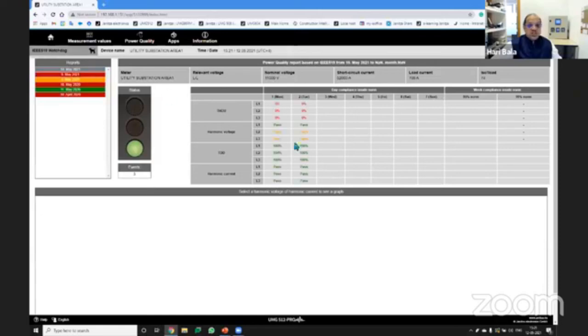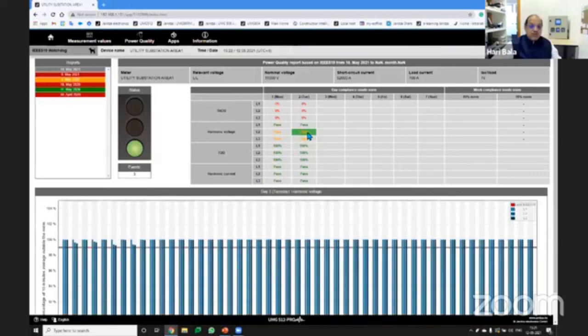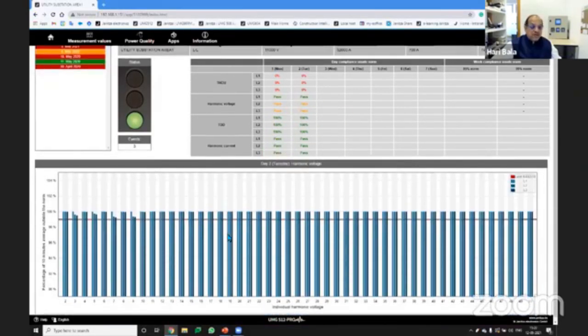For this, I have it installed for 2 days. Since I'm using a single phase supply, it can be wrong, but the essence of what I wanted to show you here is THDU, harmonic voltage, TDD, and harmonic current. If I want to see where my harmonic phase voltage is failing on a daily basis, here it is not failing, it is just touching the red line, so it is not going down. But it is not 100%, so it is showing orange, but still we say the standard is getting passed on the daily basis.